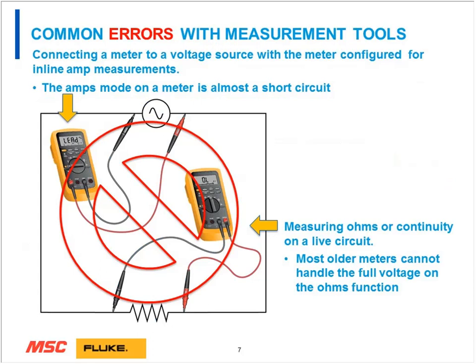Here are some common errors with measurement tools. First of all, you need to be aware of the test equipment that you're using. In many cases, someone may borrow a piece of test equipment because theirs is either in the shop or they forgot it somewhere, and they borrow a buddy's. The problem with that is you don't know the condition of the case or the fusing. If you're making a current measurement, which is in fact in series with a conductor or the loads, that could give you a direct short. And some people don't put in the right type of fuse, and it doesn't blow fast enough to extinguish any type of arcing situation, and that can be very dangerous.